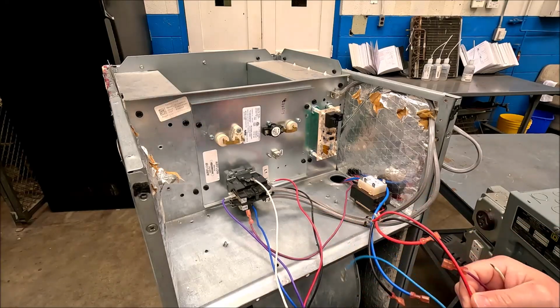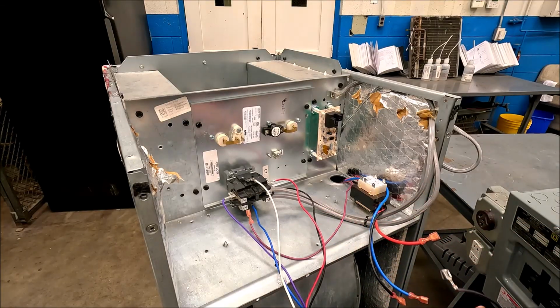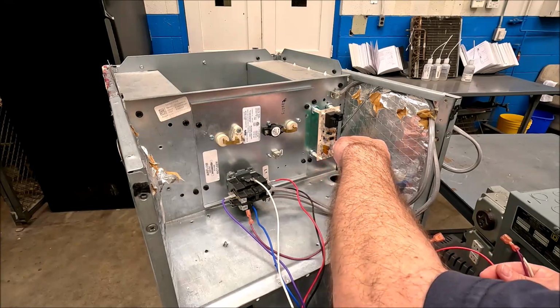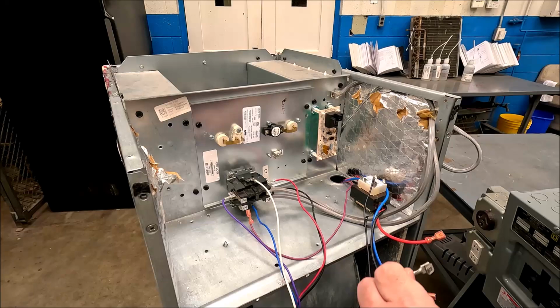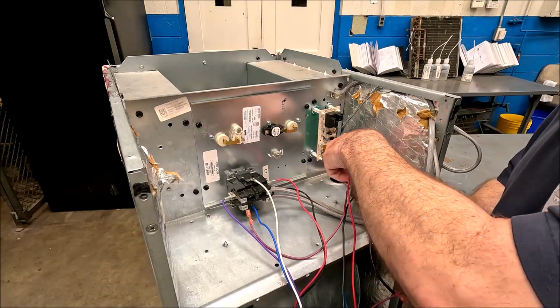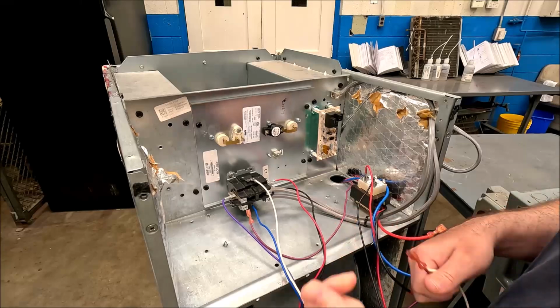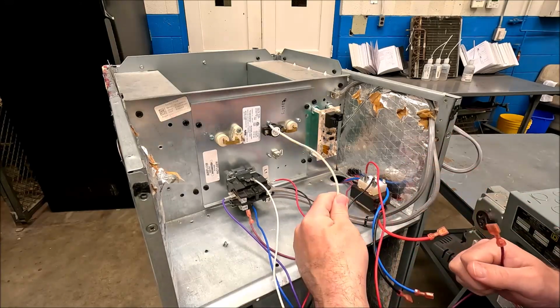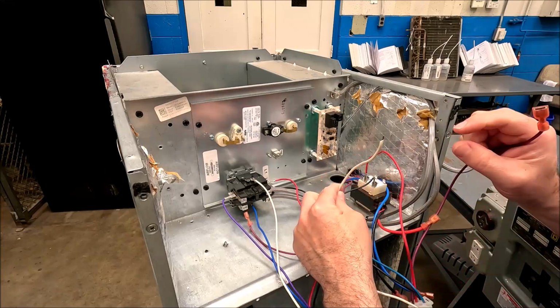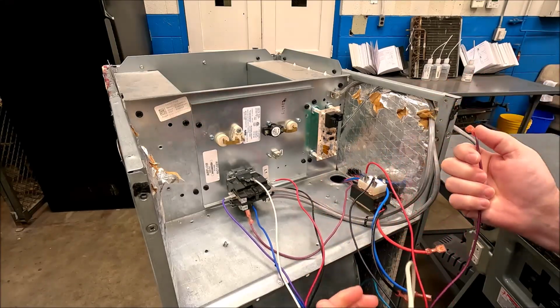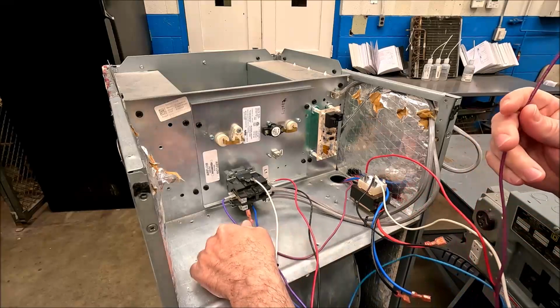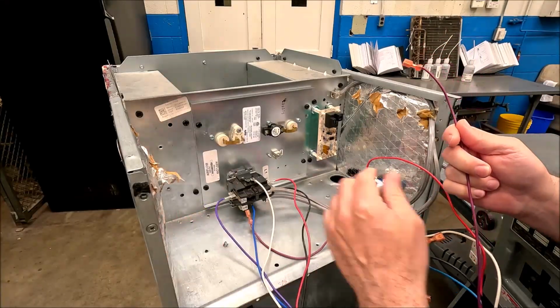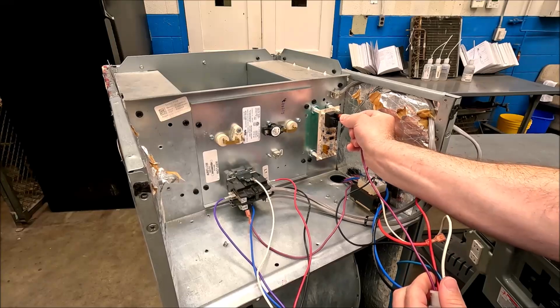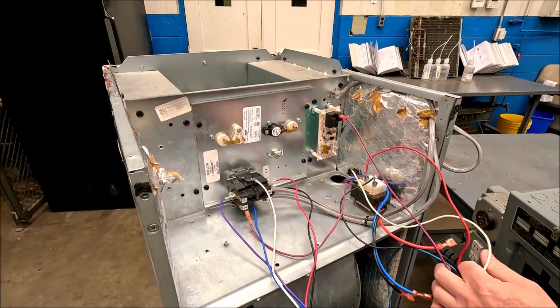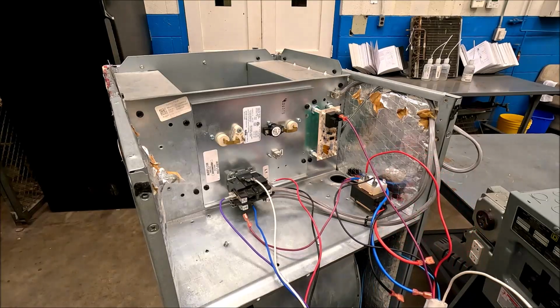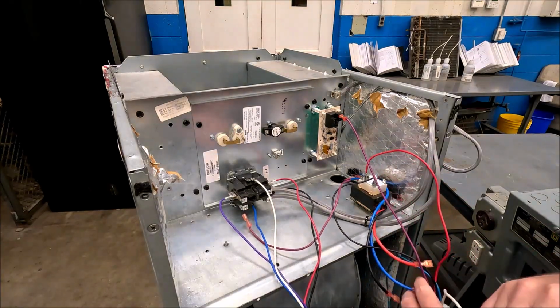So red and black, according to the diagram, is going to go to our transformer primary side. So I'm going to put the black on the common, and this red, since I'm a 208 here in the shop, I'm going to put on the 208 tap. This white would be where I would use a wire nut to connect to my field white wires. This purple wire that originated on the leaving side of the heat switch is going to go to the normally closed. That's your terminal 3 in the plug.